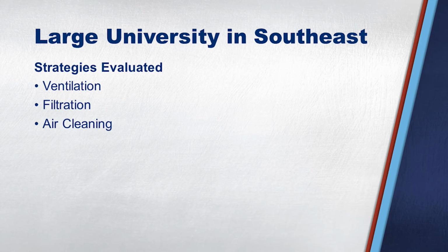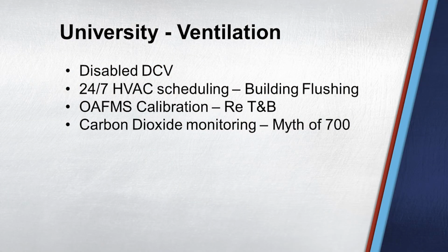And then this one was a large university in the southeast. They looked at a few different strategies. First thing they did when it came out is they disabled demand controlled ventilation, following what ASHRAE said: hey, try to minimize that, get your outside air. But then they turned everything into 24/7 flushing. They were reading that article by an individual and they turned it that way. They did calibrate their outside airflow measuring stations because they knew that it was a key component.